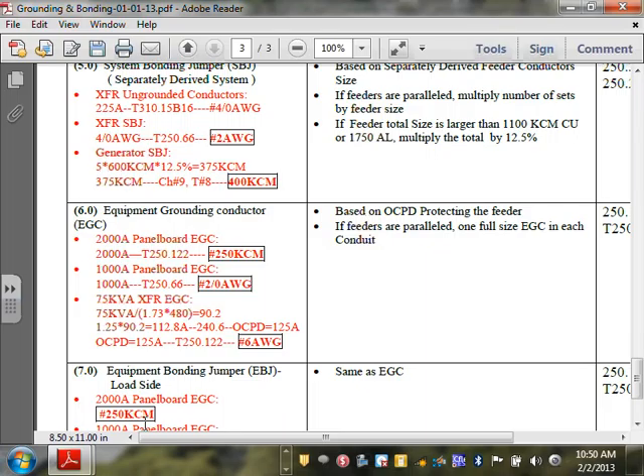If you run 3 runs, then you need 3, one with each. All the same size. That's the most confusing thing because we don't parallel. The idea, one conduit. Now if you put them all in one conduit, do you do that? 3 runs. I think what he's saying is the size of that wire would be the same no matter how many conduits you use. Absolutely. The number will be different.